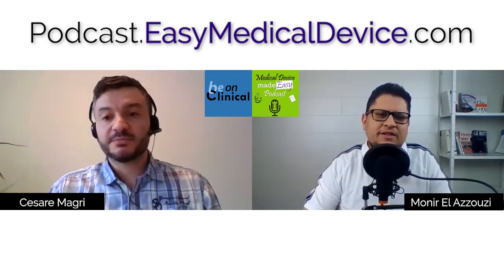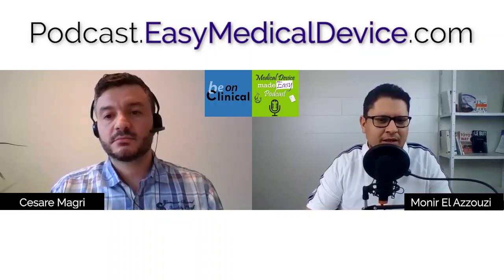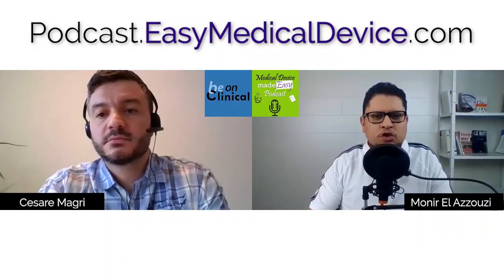I think it is also important to mention that when we have a device that is used by a user or a lay person, and because now there is this vocabulary of lay person, there is maybe also some additional test or additional proof that you have to provide in terms of usability. So to say that yes, all the information that I provided in my file is suitable for this kind of user. So showing which user is really using the device can be critical for the notified body, just to say, okay, it's not a professional that will use that, it's a lay person, a person that is common, anybody, if I can say.